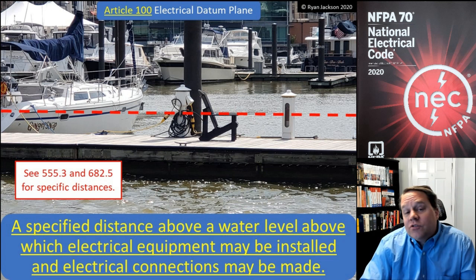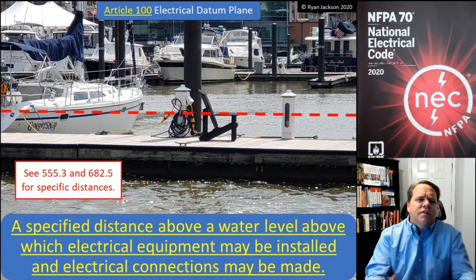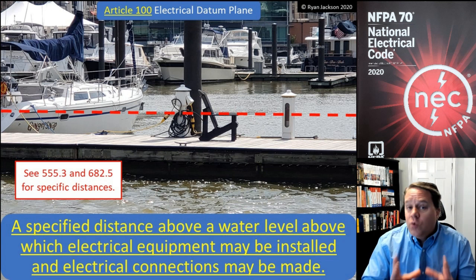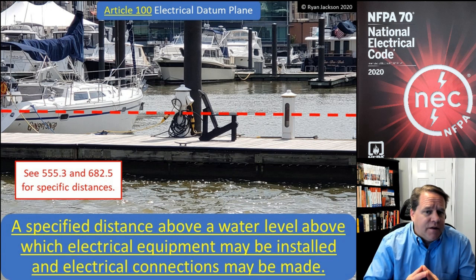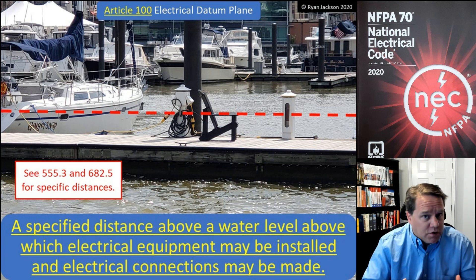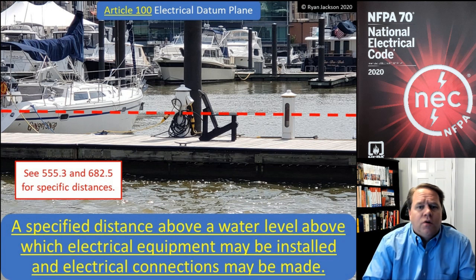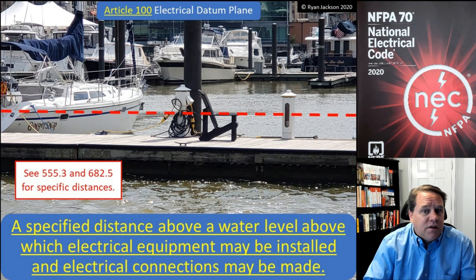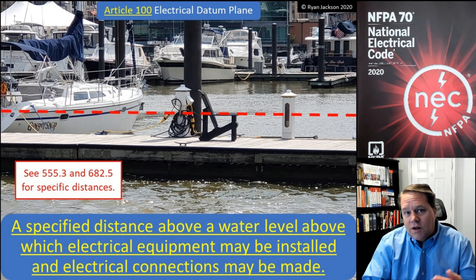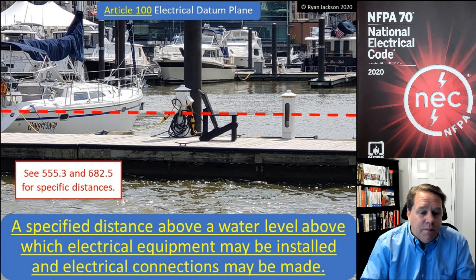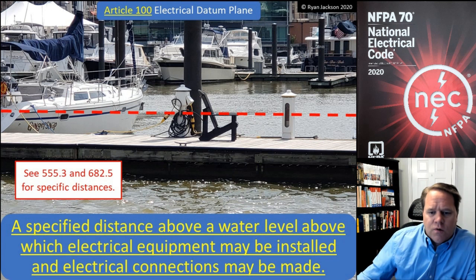Next up we have electrical datum plane. This term is only used in two articles in the NEC: article 555, which covers marinas, boat yards, floating buildings, and similar installations, and article 682, which covers natural and man-made bodies of water. The electrical datum plane is defined as a specified distance above a water level above which electrical equipment may be installed and electrical connections may be made.